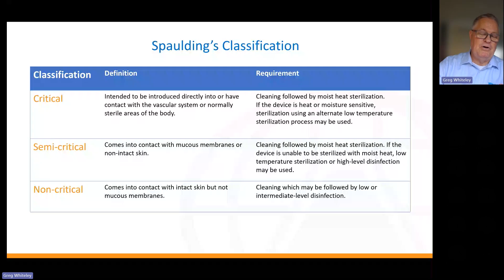It always starts with cleaning. The number one cause of failure for sterilisation or disinfection is failure to clean. If you don't clean correctly, you elevate the risk of failure by literally orders of magnitude. And that's because so many of the bugs that we're worried about will be alive inside biological soils. We won't have time today to fully deal with things like what soils are which and which pose the most risk, because in fact you should look at all of them as posing a risk, and they should all be removed to the best possible level. Disinfection, as I say, is mainly for heat sensitive reusable medical devices, but there may be other contexts.